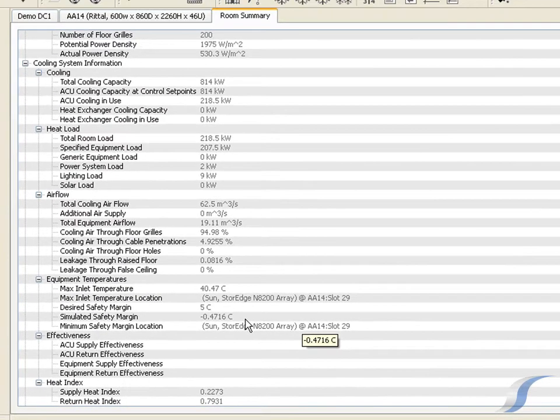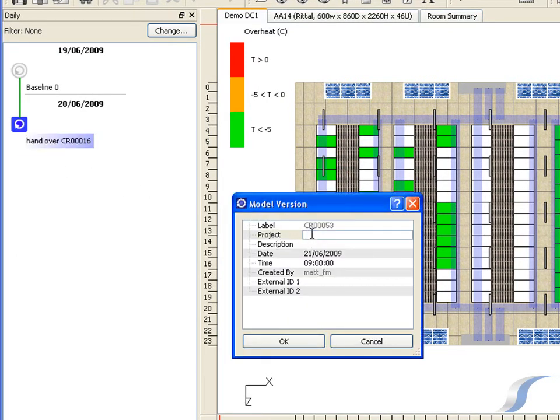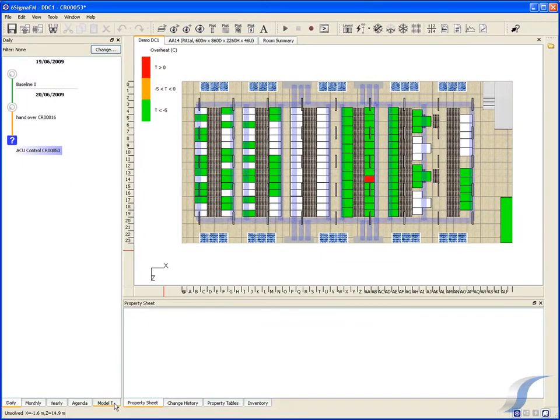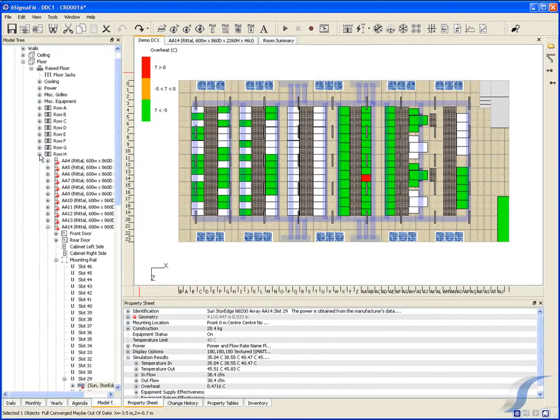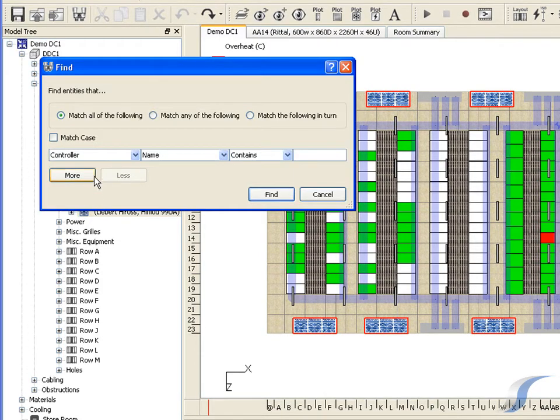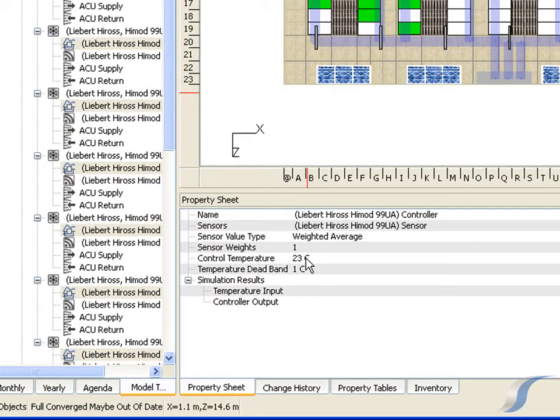The traditional approach to these hotspots and overheats is to turn down the ACU set points. Let's do so in the software to check whether it will work. In theory, reducing the set points by 1 degree C should stop the overheat — this can also be seen easily from the Room Summary. Note, however, that a 1 degree reduction won't achieve our 5 degrees safety margin.